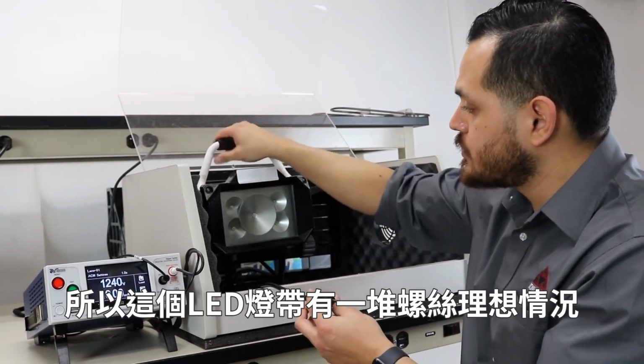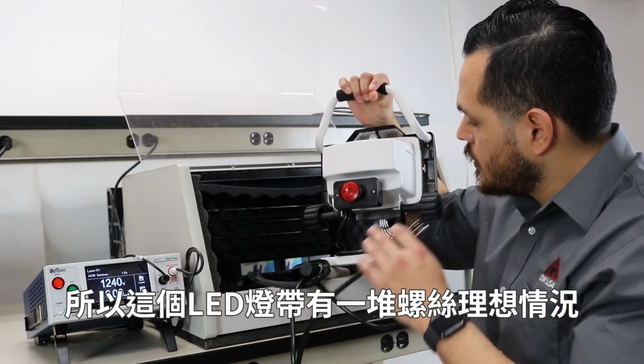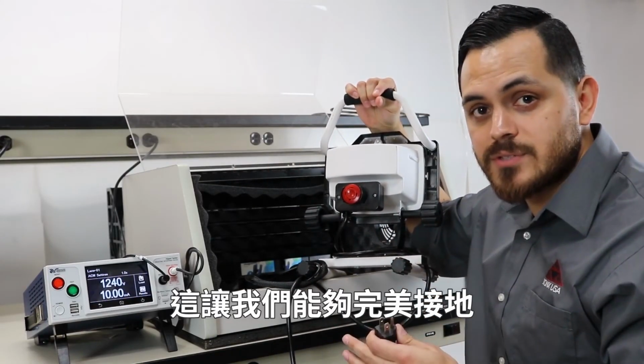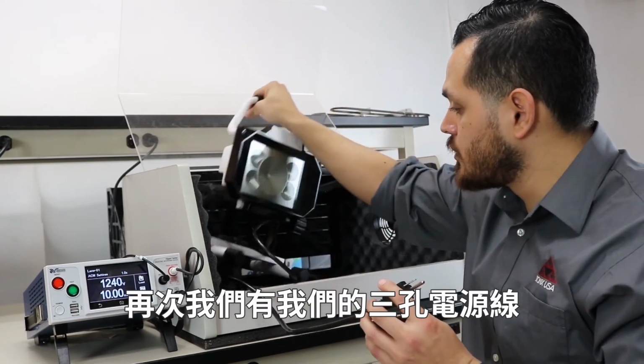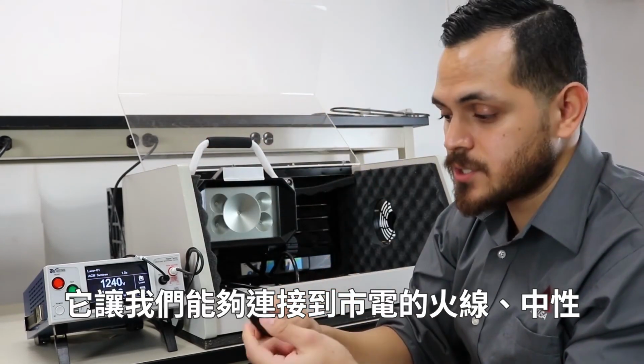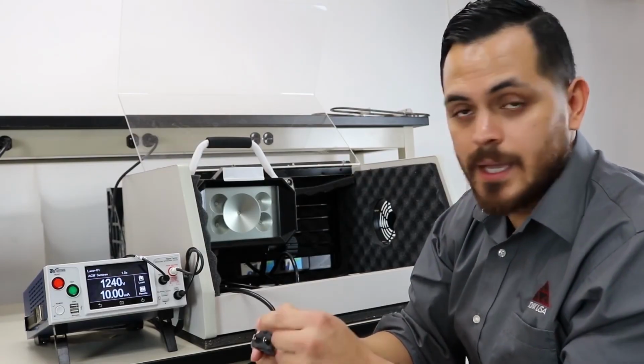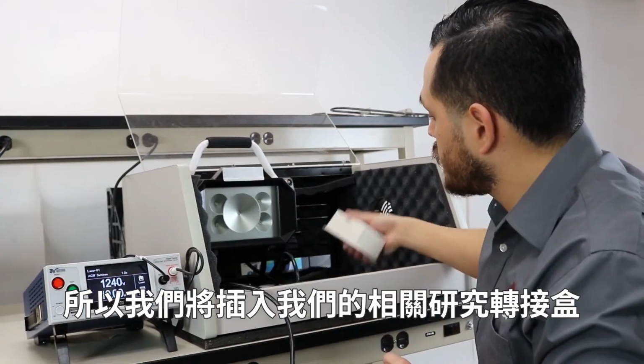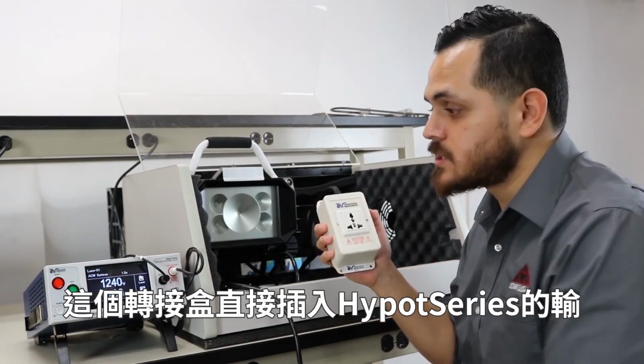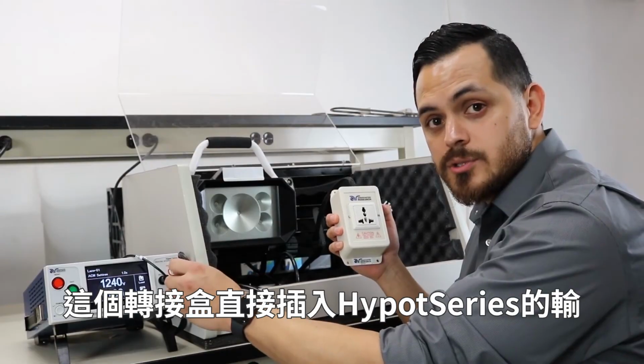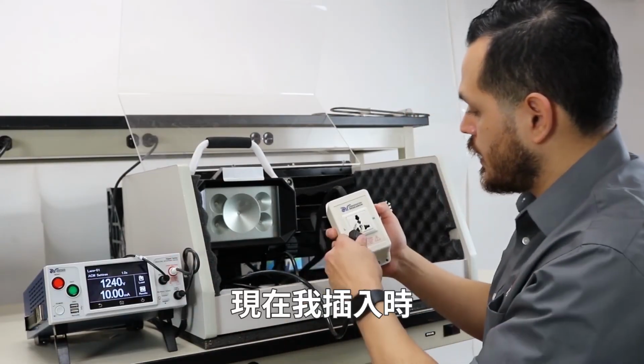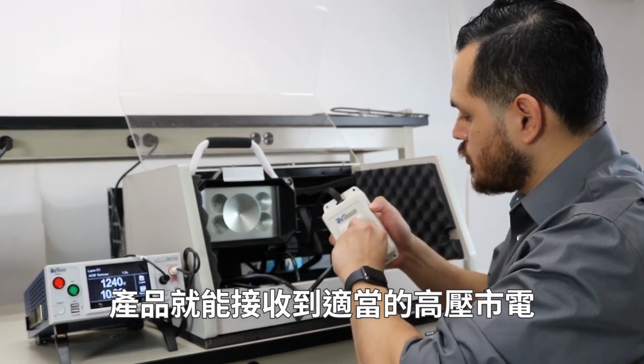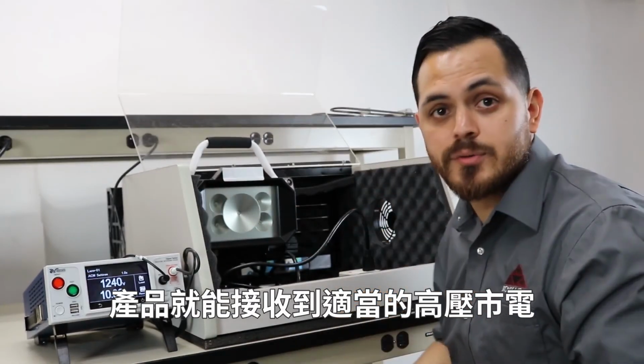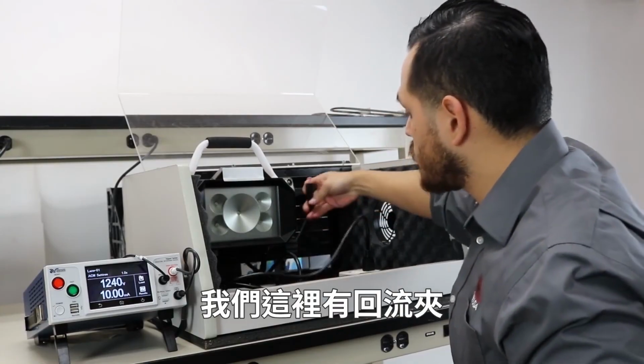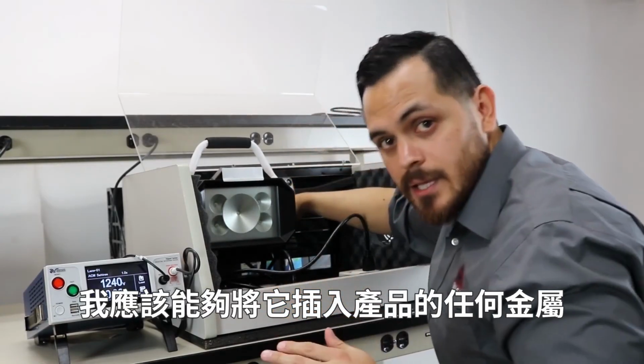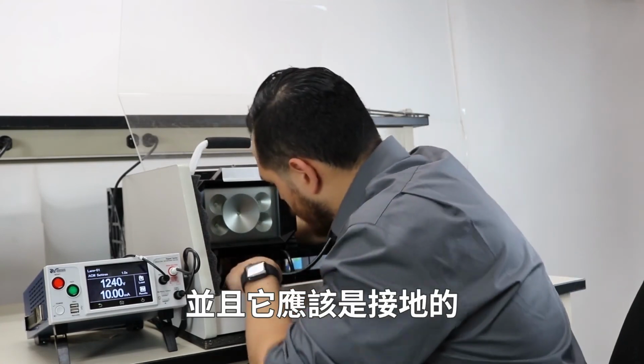So this LED lamp comes with a bunch of screws which ideally are grounded, which gives us perfect access to ground. And again, we have our 3-prong line cord, which gives us access to the mains, line and neutral, and the ground stud. So we're going to plug into our Associated Research adapter box. This adapter box gets directly plugged into the outputs of the Hipot series. And as I plug in, now the product can receive the appropriate high voltage to its mains, and we have our return clip here that I should be able to plug into any metal part of the product, and it should be grounded.